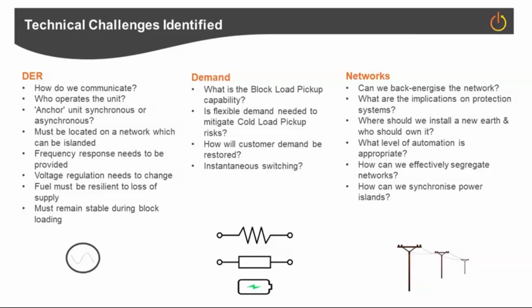The DER, the generator, the location of it is key. It has to be located on a part of the network which can be split up, islanded, segregated. It has to be able to deliver frequency response. A lot of these distributed energy resources are not; it's not normal for them to be in frequency response mode. So to form a stable power island, they're going to have to be able to do that. They have to regulate voltage, and the way they regulate voltage is going to need to change compared to what's done currently.